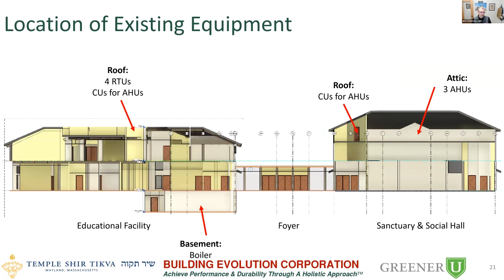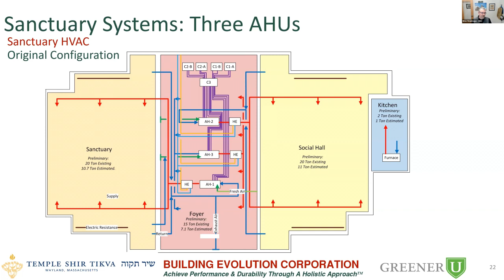For example, this was a sketch I put together for just the sanctuary and social hall side of the building, to try to make it easier to understand how the actual space was controlled and conditioned. Still didn't make it that much easier. But here's the actual sanctuary side. You have air handling units conditioning the spaces, but they are all disconnected from the boiler on the other side of another building that's providing heat to them, and cross-connected to each other with ductwork.